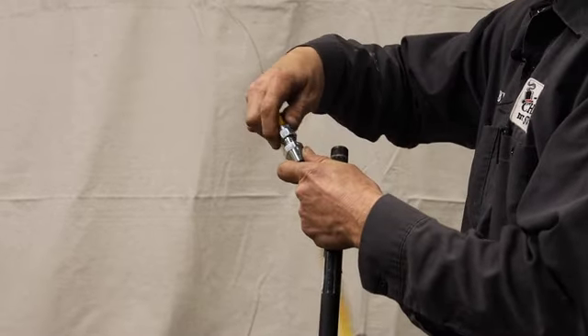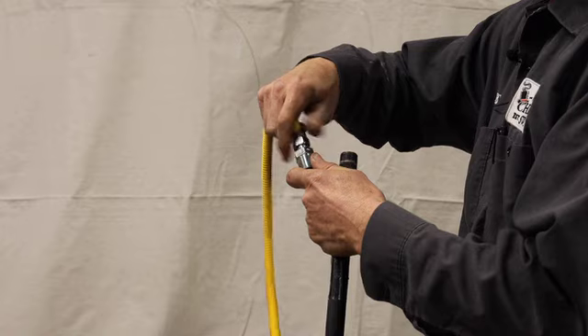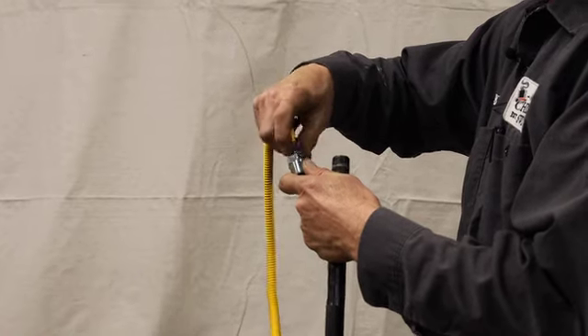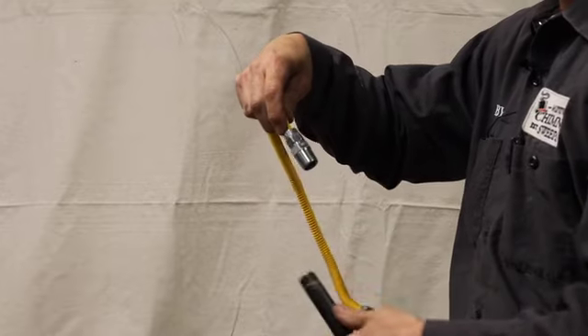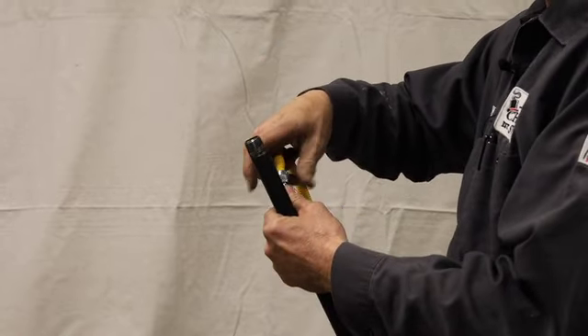The important thing to note is when you're doing compression fittings like this, you can never put the compression fitting to an iron pipe. That would be disastrous because it won't seat, it won't seal.